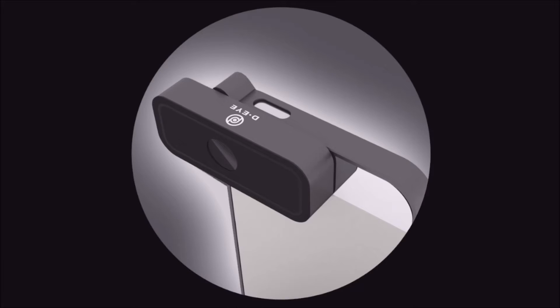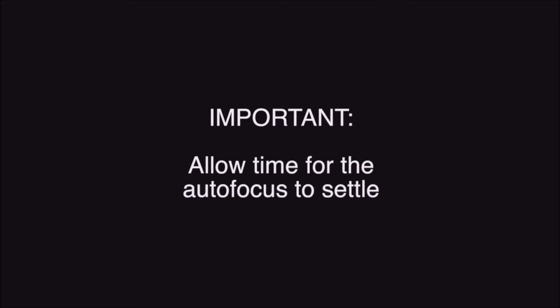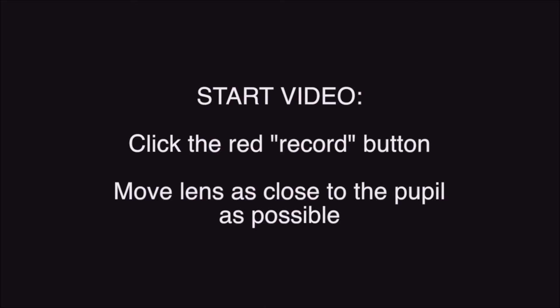Put the lens on if you haven't already and slowly approach the eye. It is very important to practice the following procedures so that the autofocus of your smartphone camera has time to settle and be in focus before you start the exam. The autofocus will begin to adjust as you move closer to the pupil. At about 6 inches from the eye, click the red button to start the video and move the lens as close to the pupil as possible. When you see the red reflex from the eye, the D-Eye has been correctly aligned and focused.